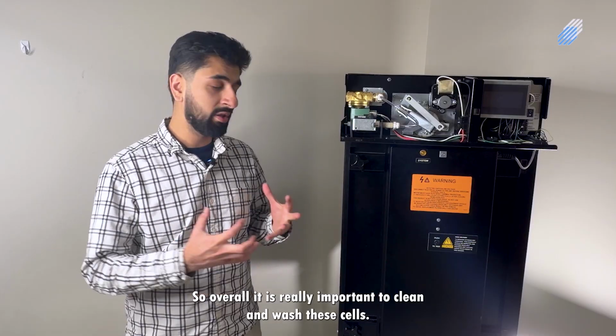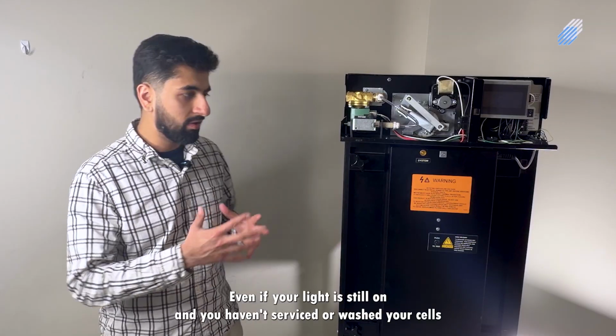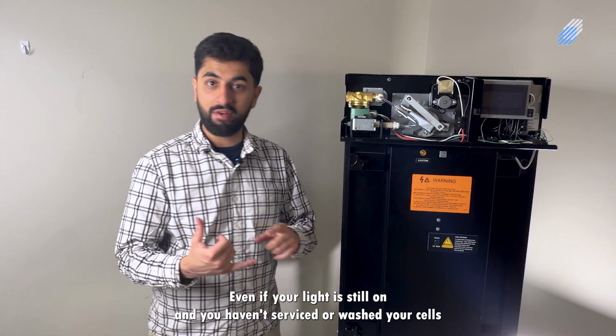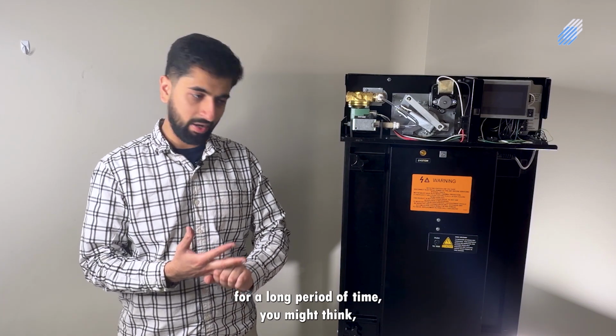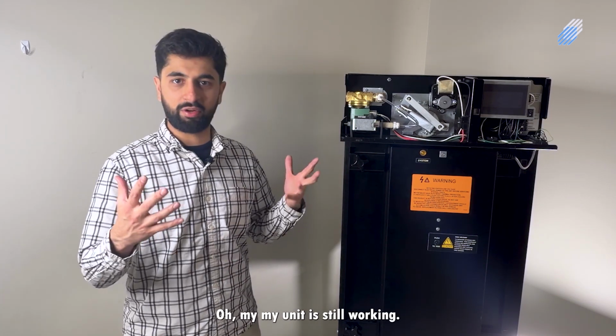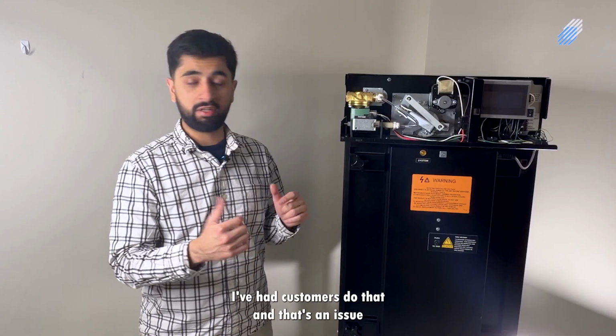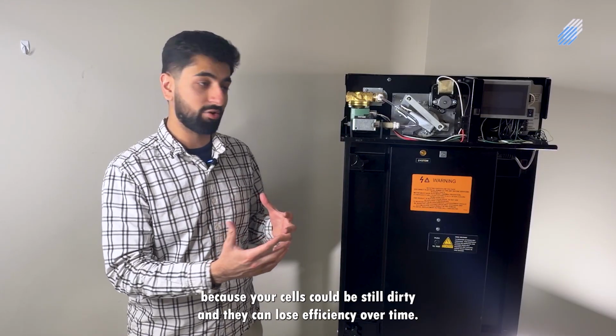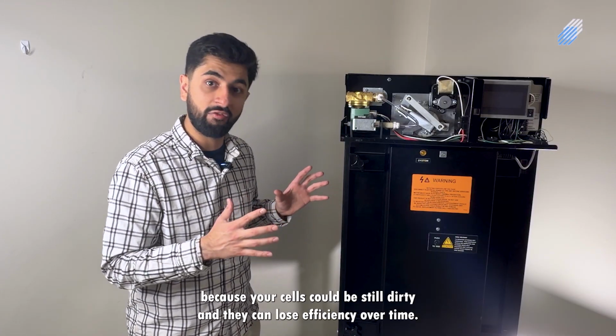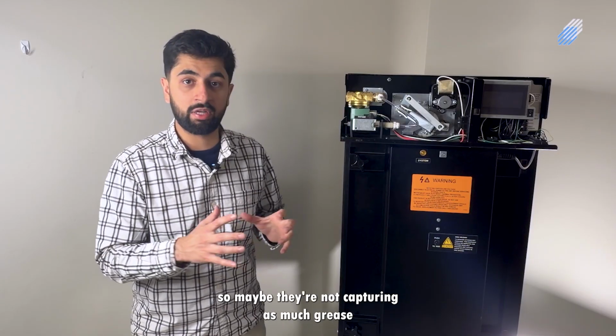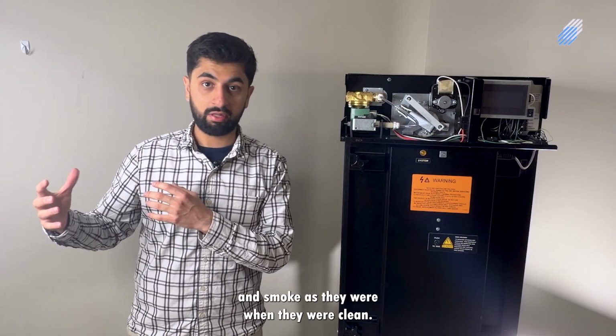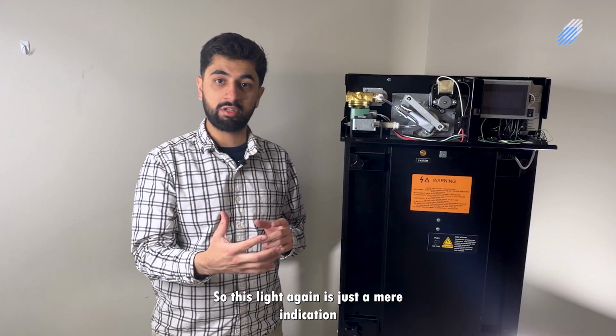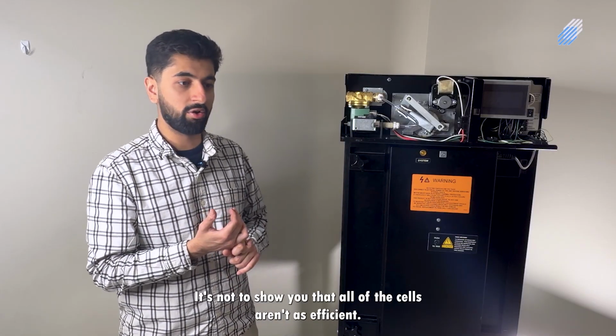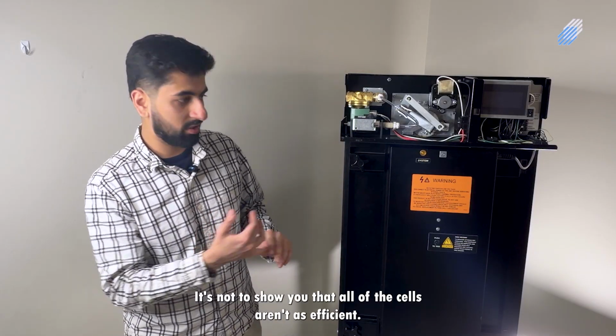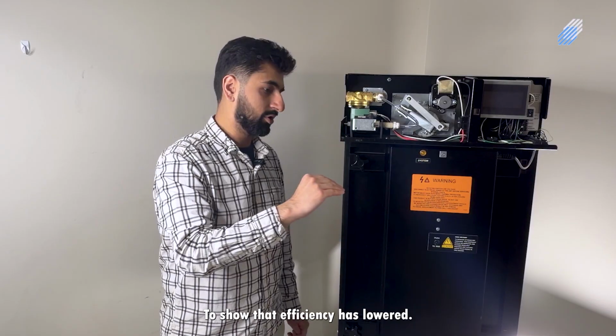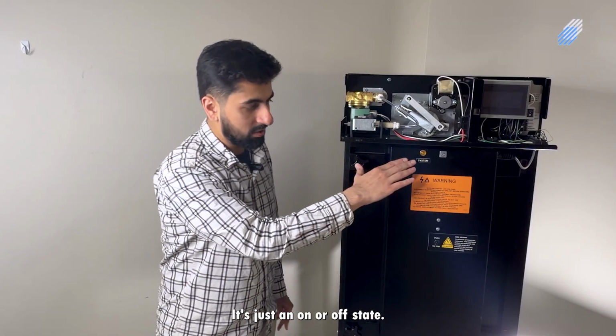So overall, it is really important to clean and wash these cells. Even if your light is still on and you haven't serviced or washed your cells for a long period of time, you might think, oh, my unit's still working, I don't need to touch it until the light turns off. I've had customers do that, and that's an issue because your cells could still be dirty and they could lose efficiency over time. So maybe they're not capturing as much grease and smoke as they were when they were clean. This light, again, is just a mere indication that the cells are being energized or not. It's not to show you that the cells aren't as efficient. The light will not go dim to show that the efficiency has lowered. It's just an on or off state.